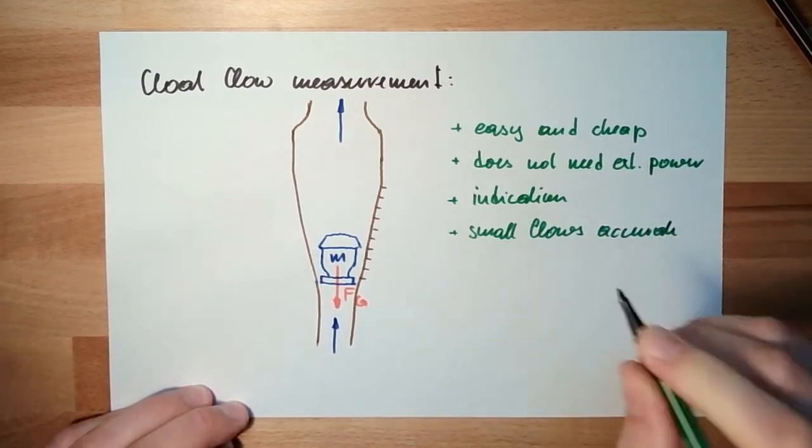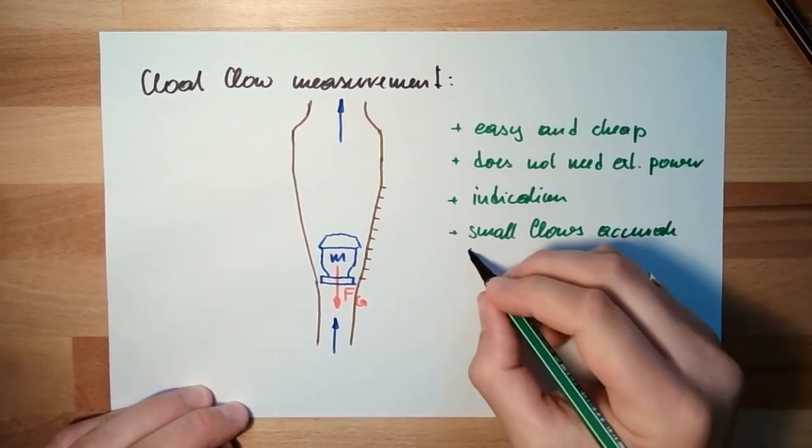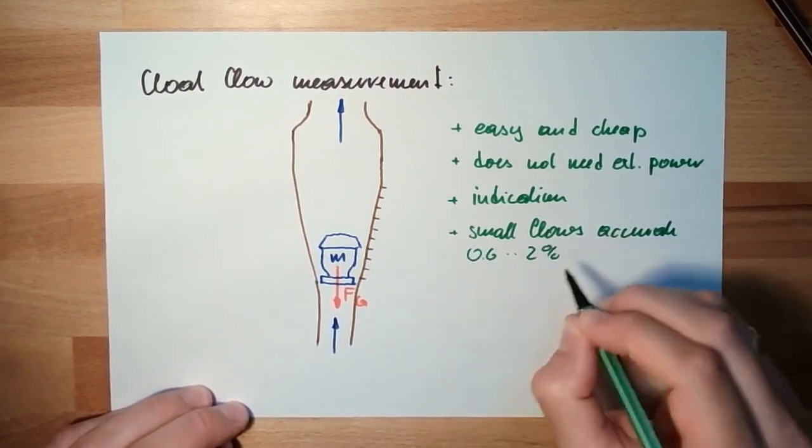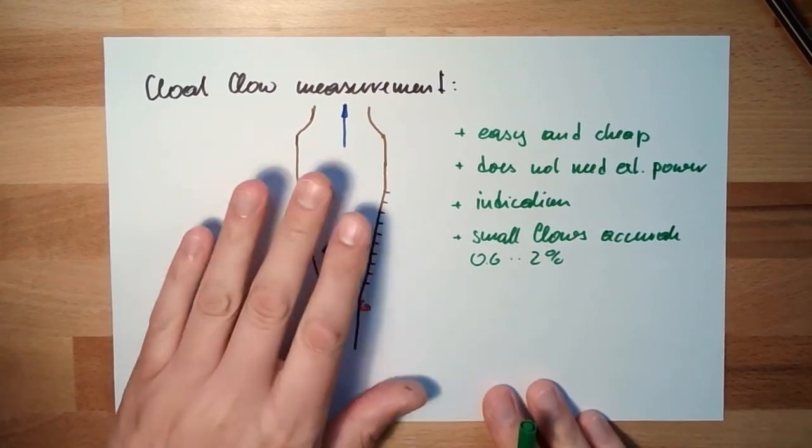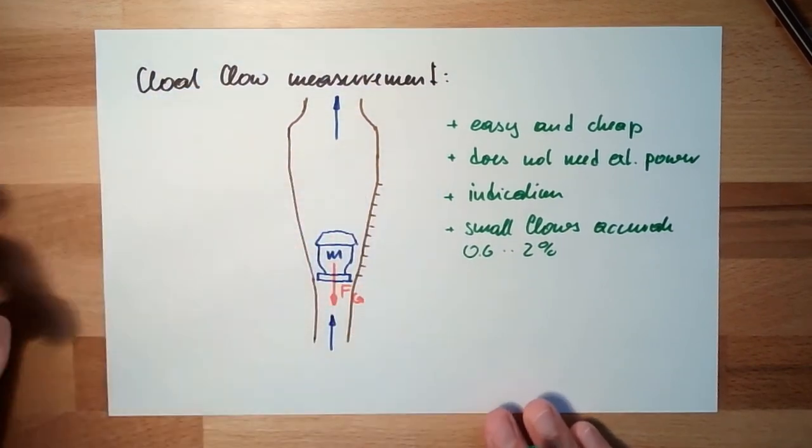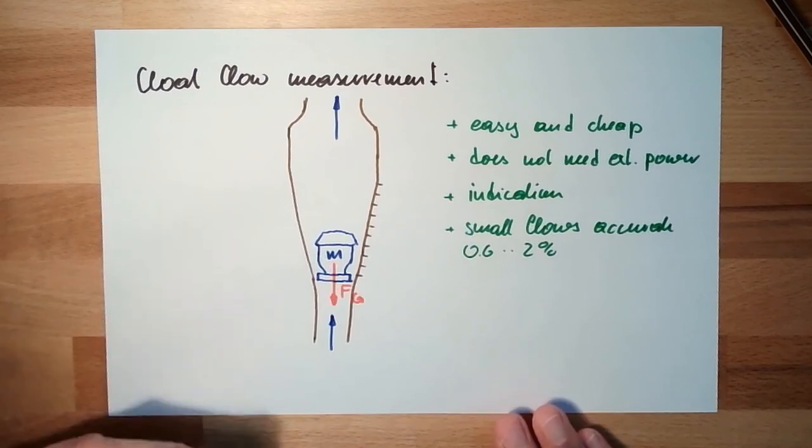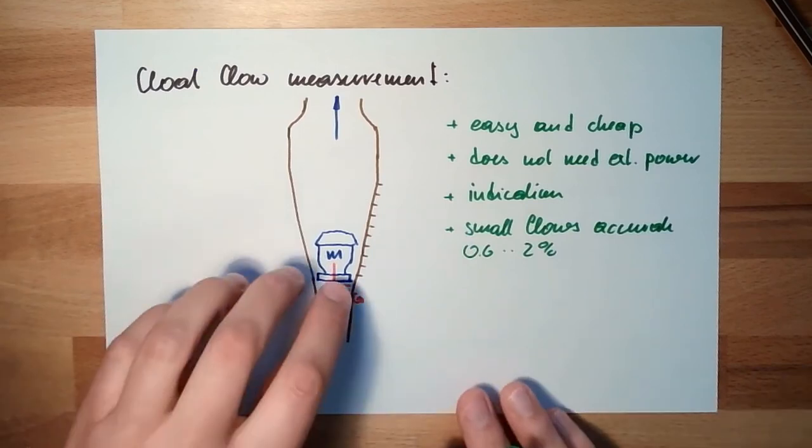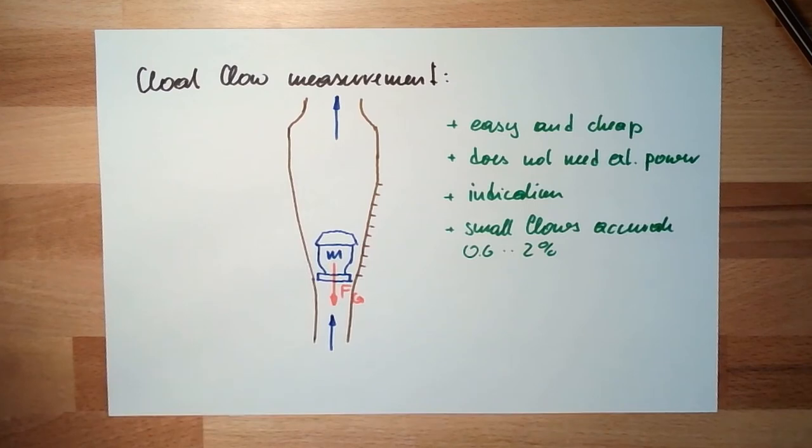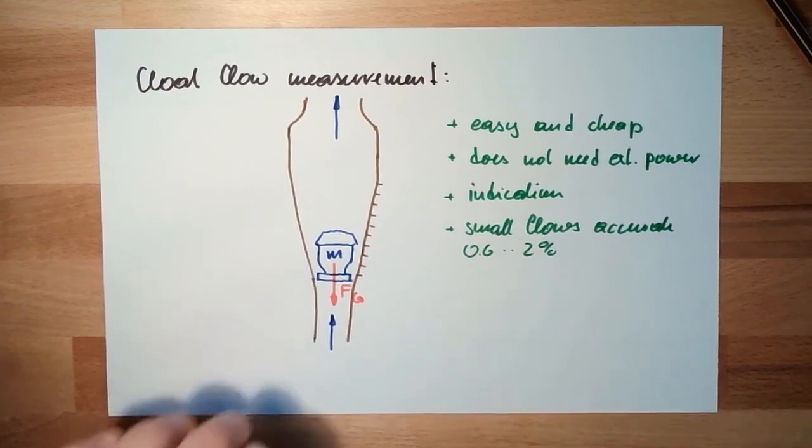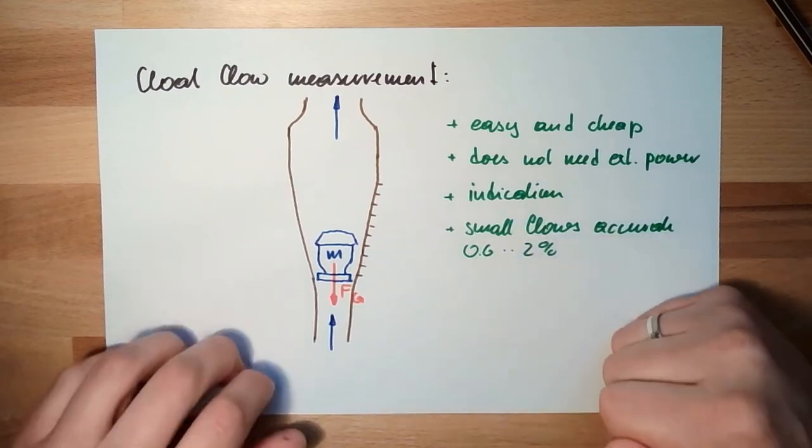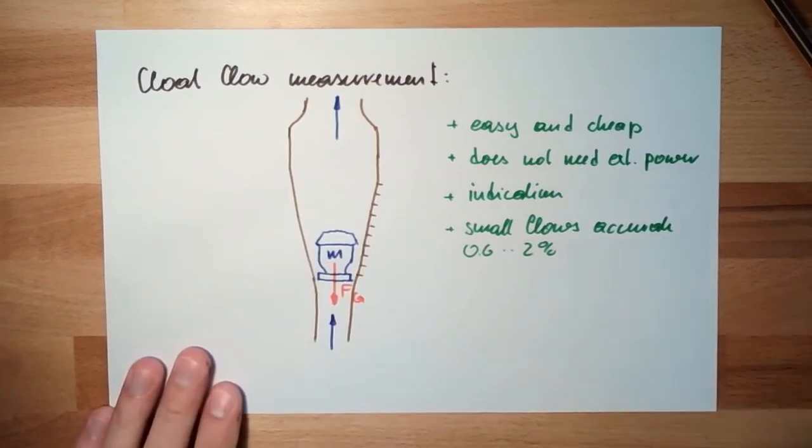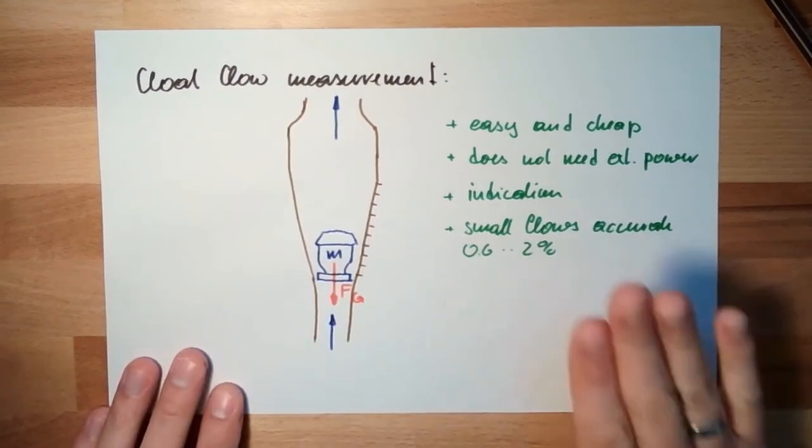Accurate - accuracy is 0.6 to 2 percent, so it's not too accurate but accurate for small flows. Last time we discussed differential pressure where small flows were a problem. Here, small flows are not a problem - it's equally accurate at small flows, and it's repeatable.